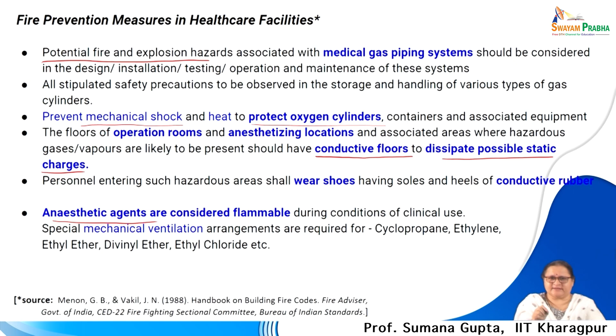Such anesthetic areas and operation rooms, expected to be associated with oxygen lines or oxygen cylinders, should have conductive floors to dissipate all possible static charges - this can be rubber or PVC.